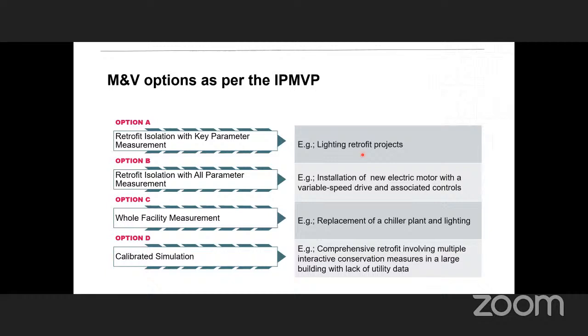With option B, we need to measure all parameters - both time and power. In that case, we need to put in place a constant power meter, or a power meter that's going to be there measuring these parameters for the whole reporting period. So we have a permanent meter measuring the lighting power, and that will be more accurate because we're not making any assumptions here.